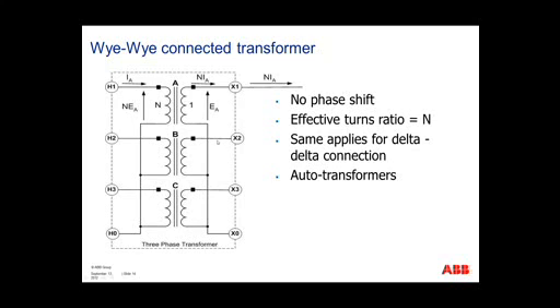Since it's a Wye-Wye connected transformer, we know that there will be no phase shift between the currents on the high side in relationship to the currents on the low side. The currents will be equal times a turns ratio associated, shown here as NIA. The same applies if this was a Delta-Delta connected transformer, and if you're in the market of using auto transformers, they too can be represented as a Wye-Wye connected transformer.